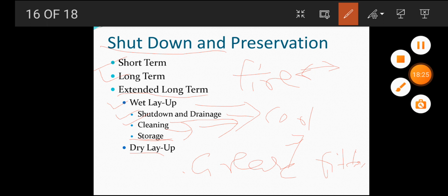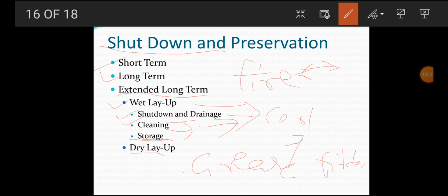So a Cortec boiler lizard is to be used for dry storage. So what is it? It is designed to maintain the proper environment for storage. So it is important to seal the water side tightly from the outside environment. Before putting your boiler back into operation, be sure to check with your water treatment supplier to determine whether any changes in the treatment are needed to compensate for changes in makeup water, operating conditions or other factors.